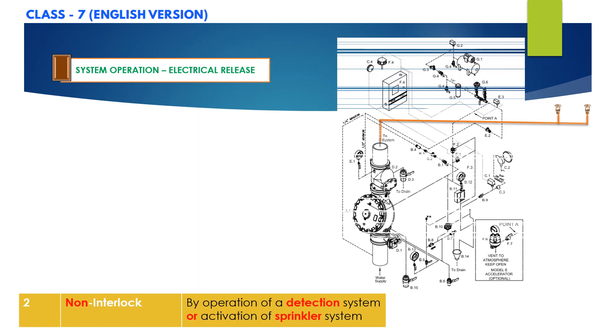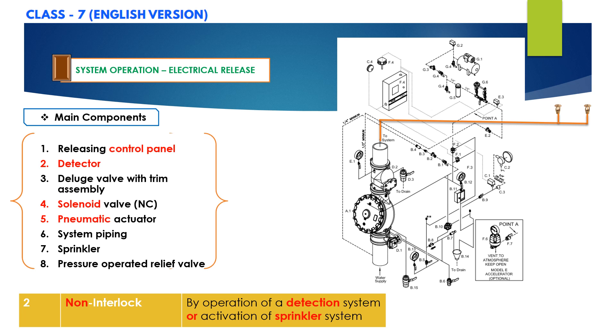Having covered the system components for electric release type non-interlock pre-action system, let us go through the system operation in detail using this schematic diagram. Initially, the system water supply pressure enters the priming chamber of the deluge valve through a 1/4-inch priming line which includes a normally open priming valve, strainer, 1/16-inch restricted orifice, and check valve. This restricted orifice restricts the flow of water to the priming line — note the line is 1/4 inch but the orifice size is 1/16 inch.